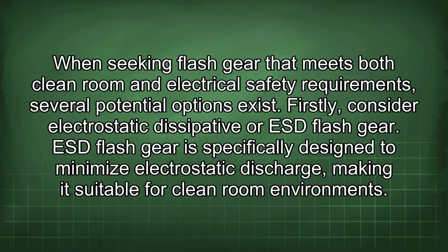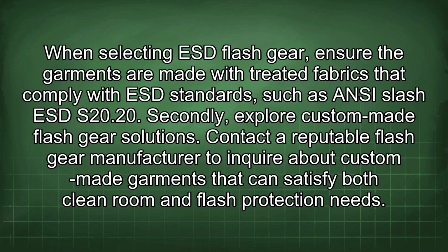When seeking flash gear that meets both clean room and electrical safety requirements, several potential options exist. Firstly, consider electrostatic dissipative or ESD flash gear. ESD flash gear is specifically designed to minimize electrostatic discharge, making it suitable for clean room environments. When selecting ESD flash gear, ensure the garments are made with treated fabrics that comply with ESD standards such as ANSI/ESD S20.20.